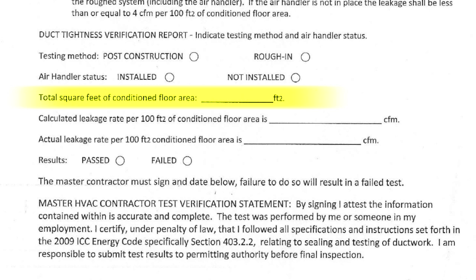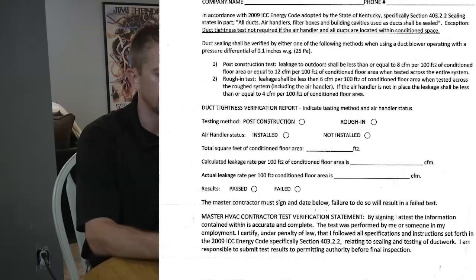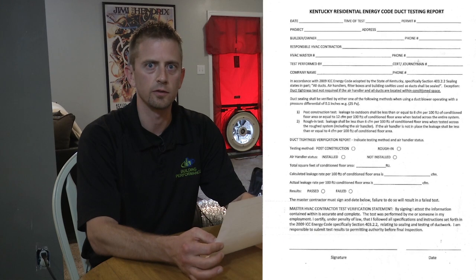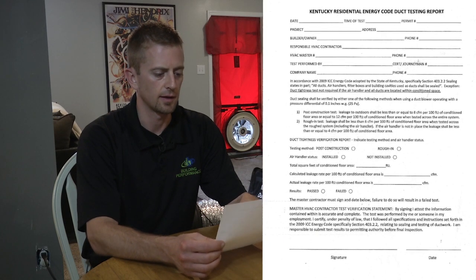So total square footage, you can put in the maximum allowable square footage for that house, and then underneath that you put the actual duct leakage that you tested on the house. So it's a simple pass or fail, either it does or it doesn't, based on that leakage maximum. And you sign it, date it, provide the report to the builder and to the building inspector, and that's what you need to do for duct leakage testing for energy code compliance.